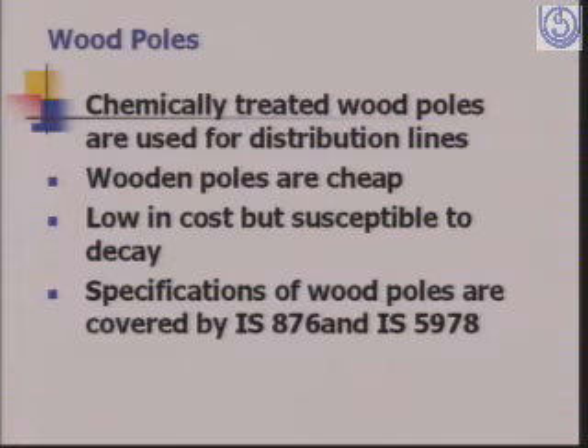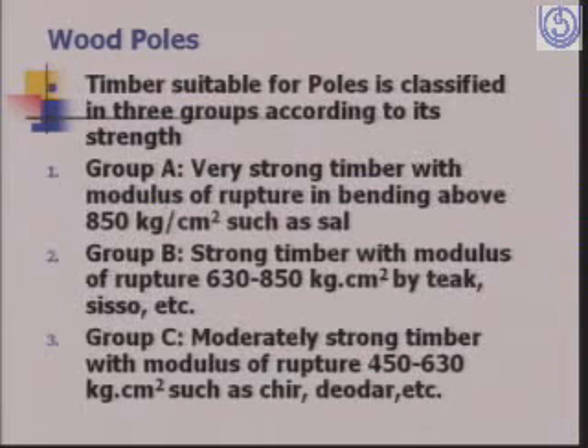Earlier wooden poles were used quite substantially, but now we are moving on to concrete and steel tubular poles. But still wood poles are used at some places. The wood poles are chemically treated and are used for distribution lines. They were used because wooden poles were cheap. They were low in cost, but they are susceptible to decay. The wooden pole at the base gets corroded, and the specifications of wood poles are covered by IS 876 and IS 5978.